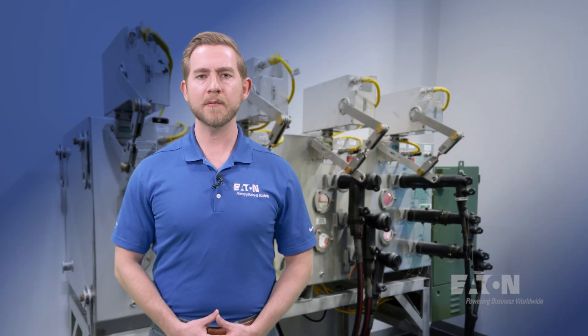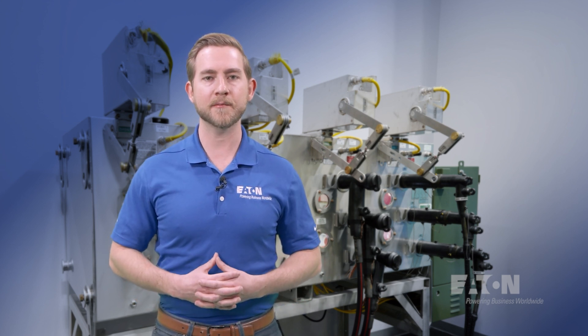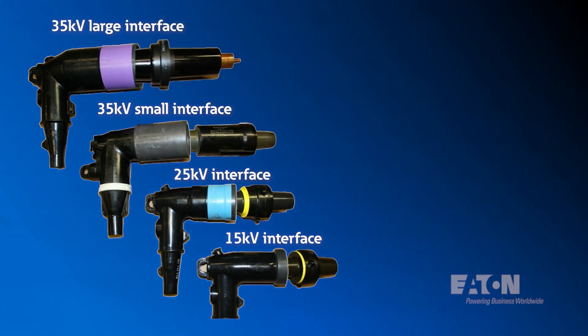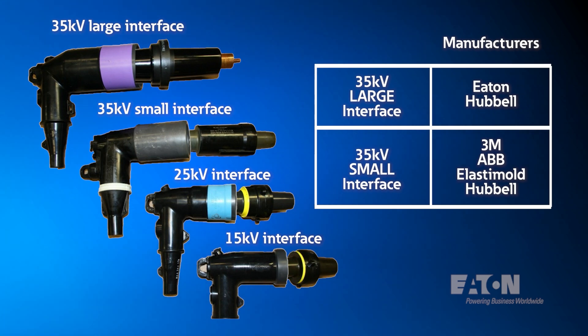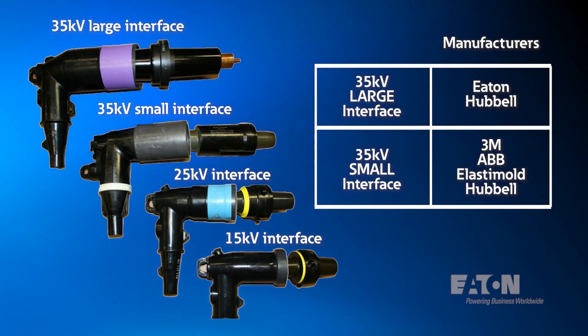Now, you're probably wondering, there are many different products on the market — how do I know which manufacturers are compatible with each other? All load break connectors in compliance with IEEE standard 386 are compatible with other manufacturers' connectors within the same interface category. Per the chart, these are the different combinations of manufacturers that are interchangeable with one another. Note that for 35 kV, small interface and large interface designs are not interchangeable if they are not the same interface size.